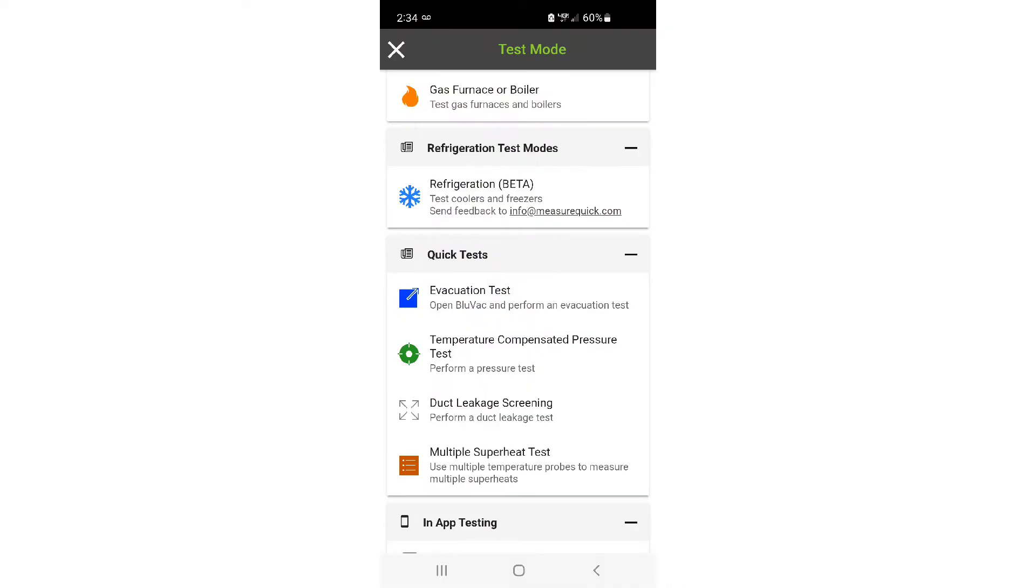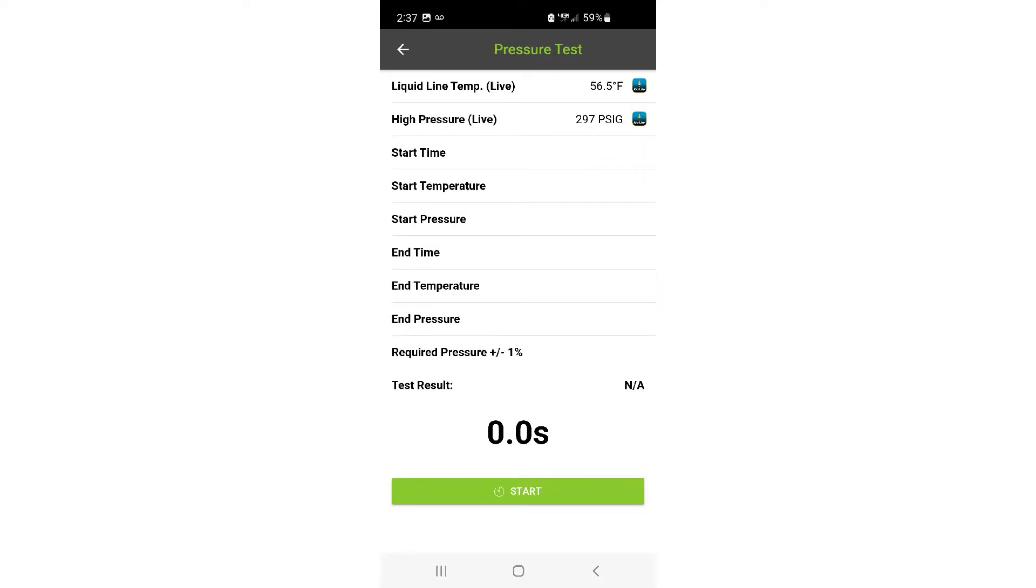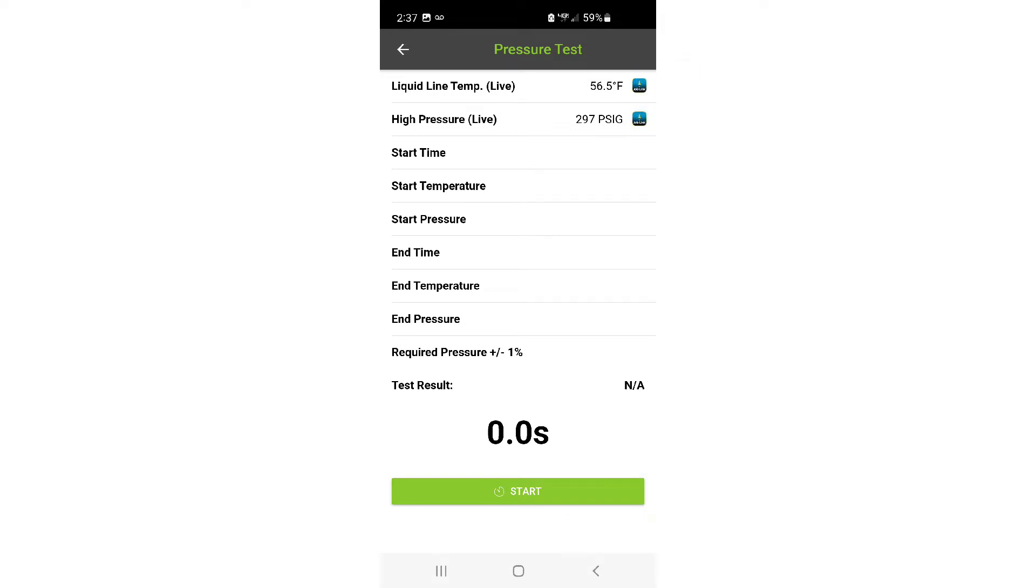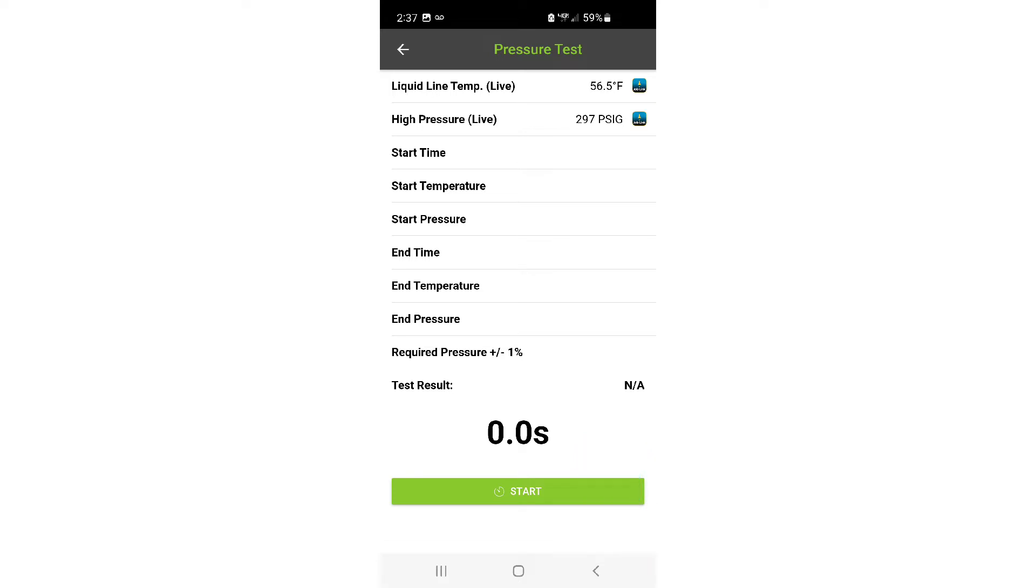Open up MeasureQuick and select the temperature compensated pressure test. The probes that are mapped to your liquid line pressure and temperature will be the ones involved in the test. Make sure they are reading correctly and then hit the start button.